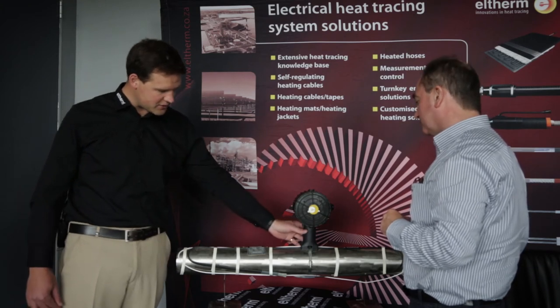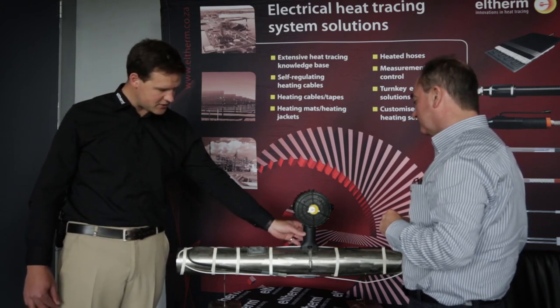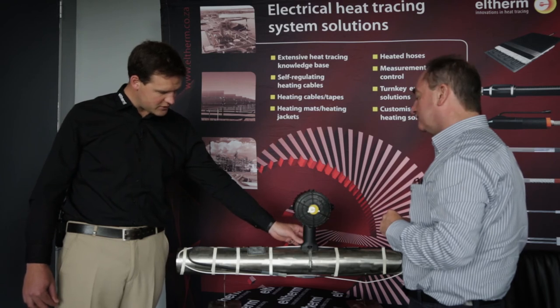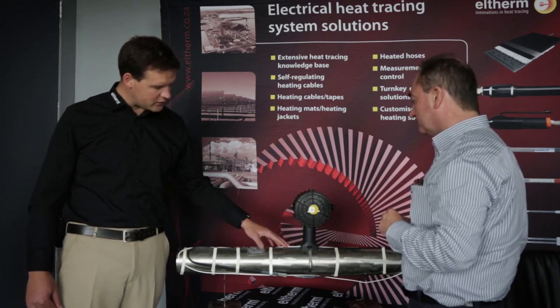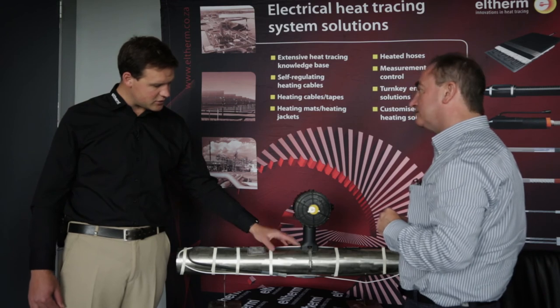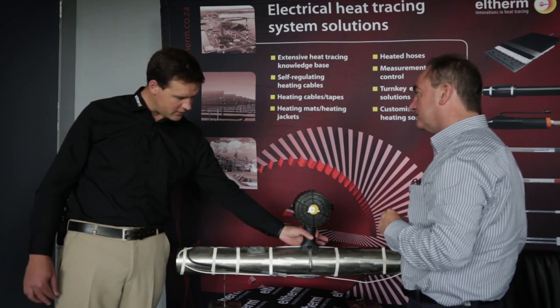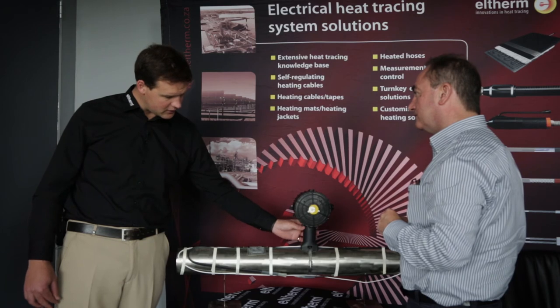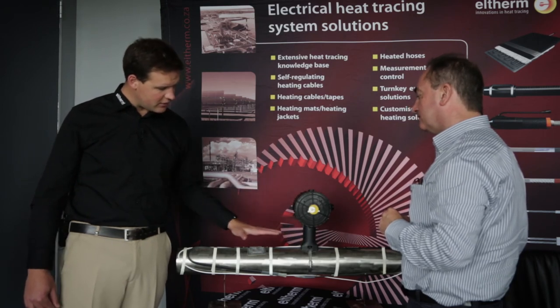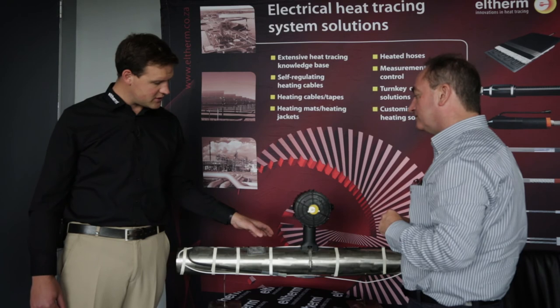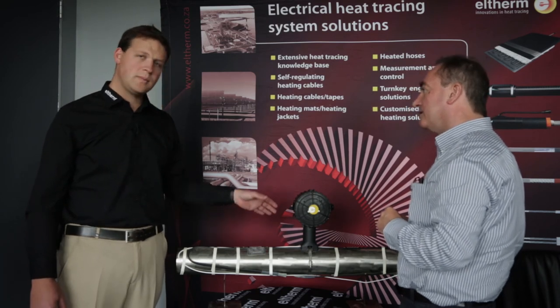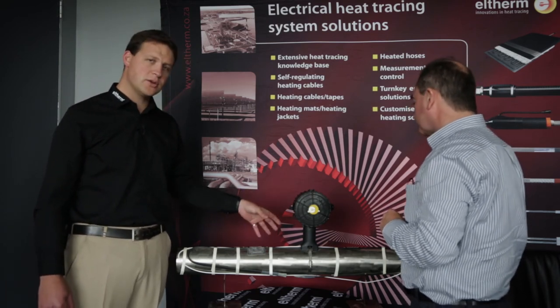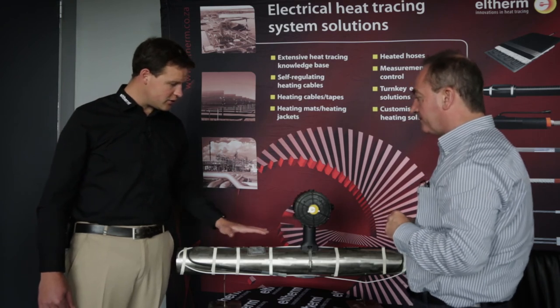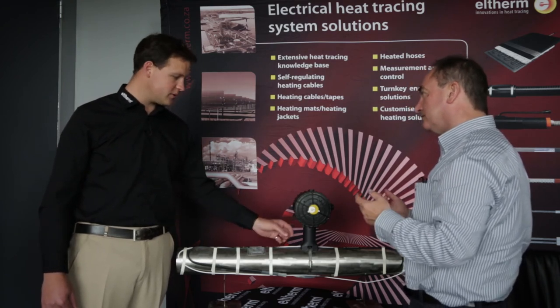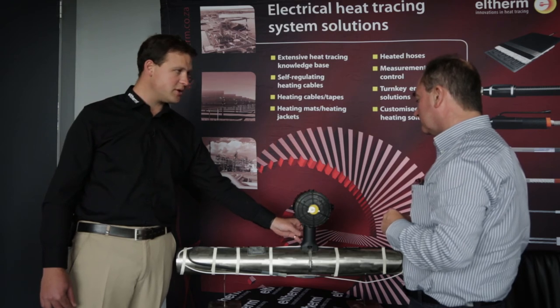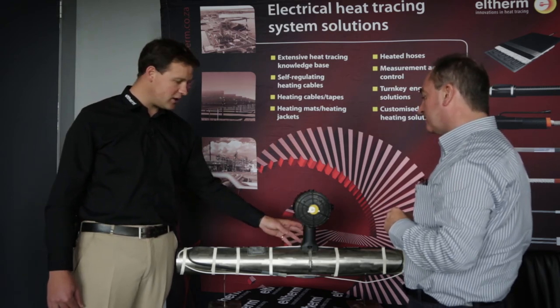This is a design that we've used in eltherm. It allows for your cables to come into the core of the body of the junction box, and because what happens after this is there has to be a layer of insulation, and a layer of cladding on top of this, you don't want to damage these cables. So this leg over here protects the cables from being damaged by the cladding and insulation.